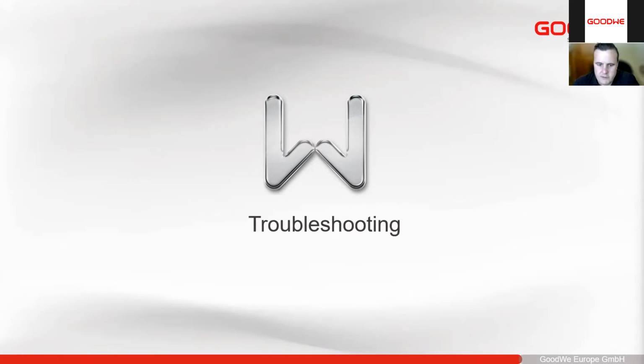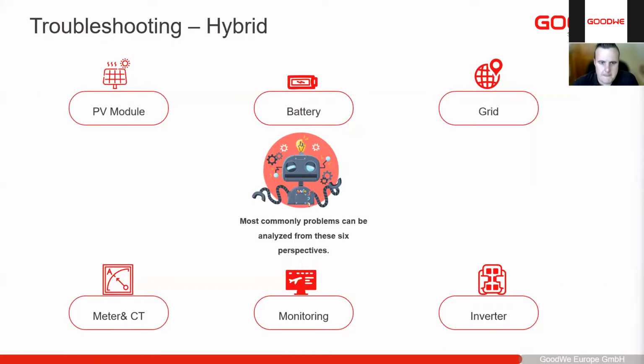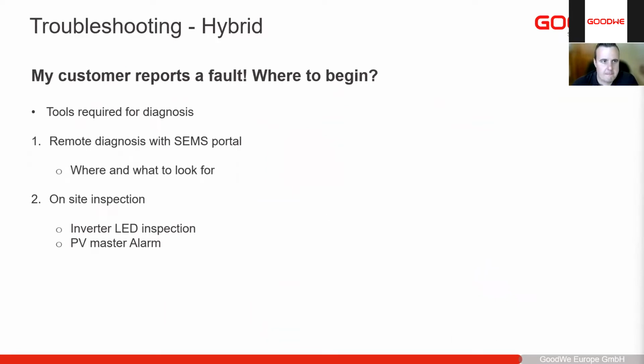So next we move into troubleshooting. Troubleshooting, as I just said, with hybrids is unfortunately a lot more complex. So most of the problems can be analyzed from these 6 different perspectives: the PV modules, your batteries, the utility, the meter and CT, the monitoring, or the inverter itself. So when my customer reports a fault, where do we begin?